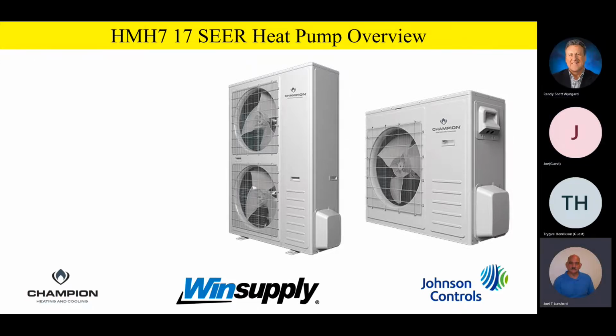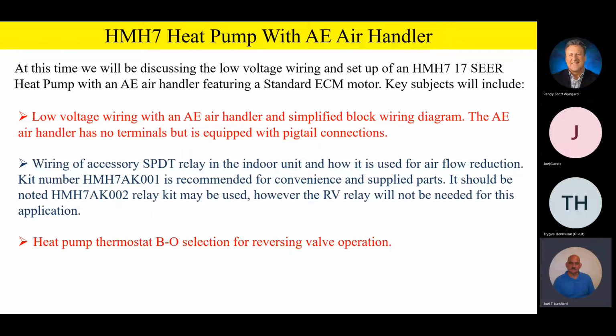Okay, so fellas, at this time we're going to be discussing the low voltage wiring and setup of the heat pump with an AE air handler. The AE air handler just features a standard ECM motor. Depending on what part of the country you're in, you may be using air handlers, you might be using furnaces, but we're going to cover all those products in our overview this afternoon. We're going to talk about the low voltage wiring with an AE air handler and a real simplified block wiring diagram that we'll display on the screen here for you.